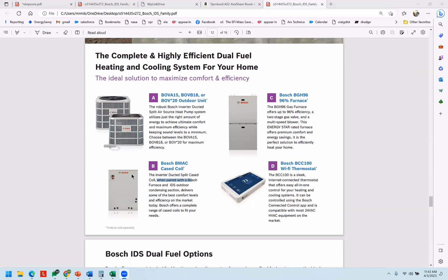Okay, so if I bifurcate the ducting for the downstairs and the upstairs, I need 2 outdoor units. And I guess one of these cased coils to reside in the basement on the furnace ductwork, and one of those slimline inline ones upstairs. Yep, that would be it. So in your case, you could be mixing and matching, because the load upstairs is 100% within the range of what a centrally ducted heat pump could do, and the downstairs is at 40,000 BTUs.